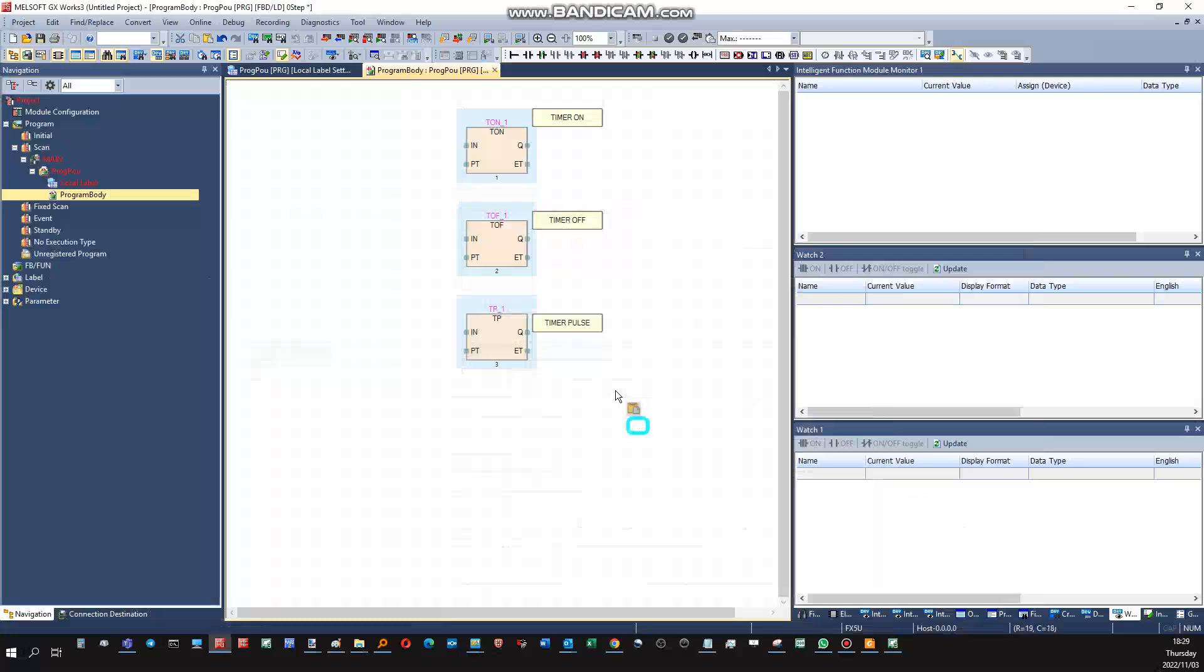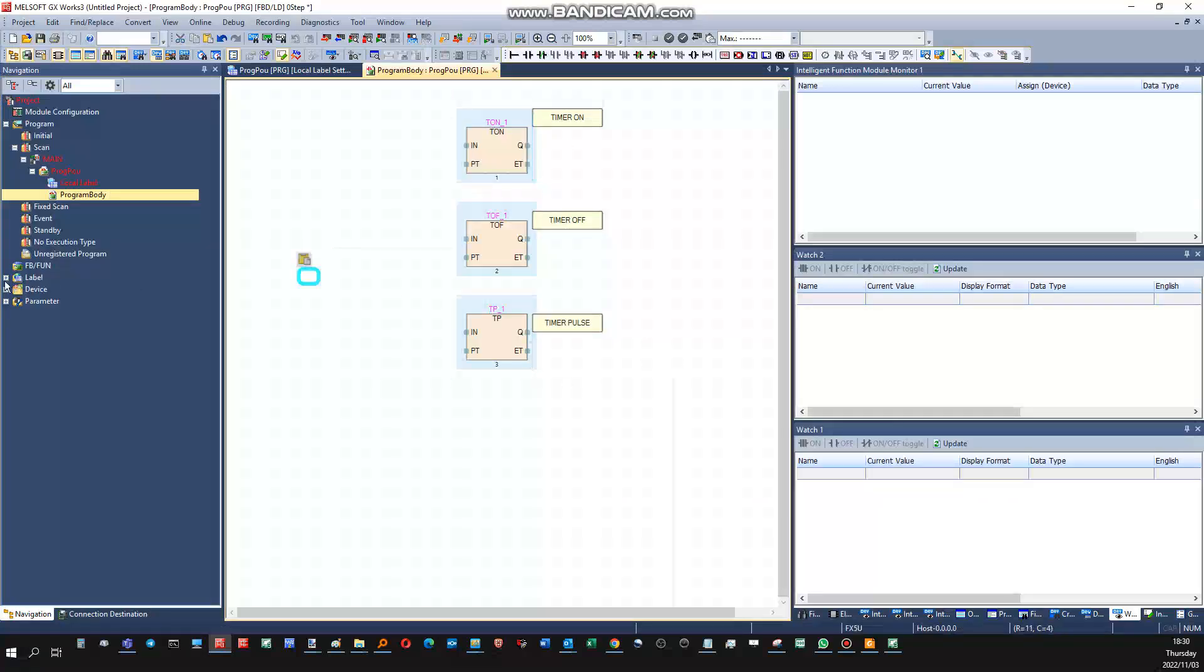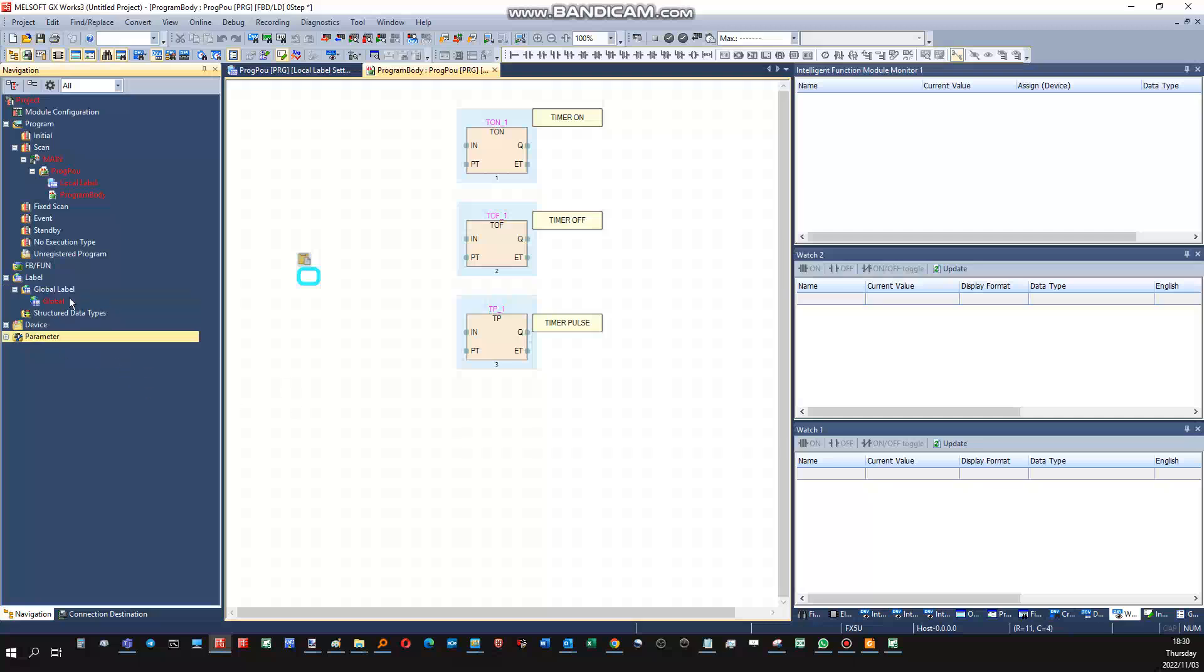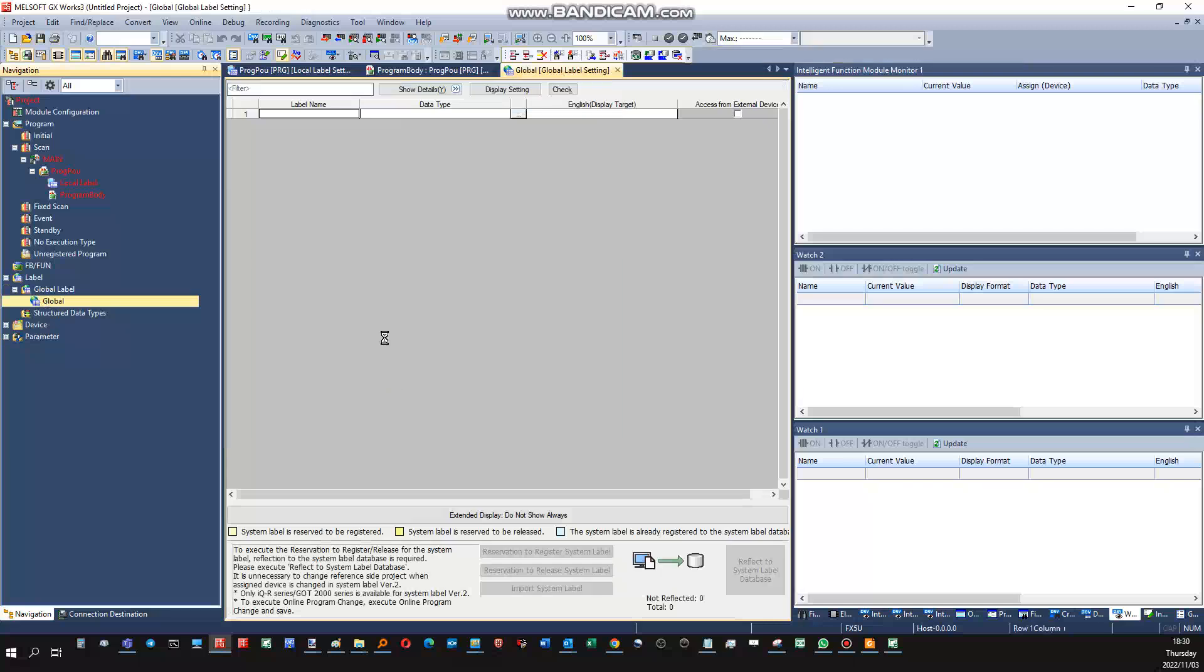We've got two inputs for each block and two outputs for each block to be configured. Since we are going to need to transfer these variables to a GT Works platform, the HMI code development GT Design platform, they will have to have device registered addresses. Each variable will have to have device registered addresses for this transfer. This is only possible with a global variable.